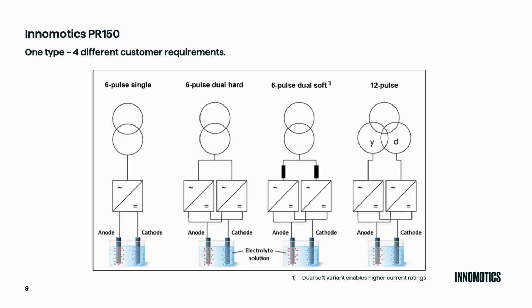Okay, maybe let's look at some more details about the rectifier. First of all, again, the different variants we can provide for this product. Starting on the left side with the easy 6-pulse configuration. That is the one we have on our booth. If you take two of these cabinets, we have the parallel connection, 6-pulse configuration. If you would like to increase the current, then we need to see the third variant. We see some input reactors, and these input reactors allow a higher current rating for this product. Or many customers would like to have the system as a 12-pulse system. Then we need a 3-winding transformer and connect even these two units in parallel. And other configurations might be possible. We now have one order where we can switch different electrolyzer stacks on the output side in different ways. That can be requested if needed.